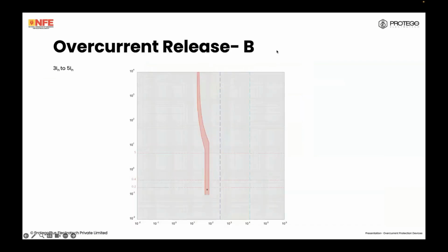Now, if we look at our overcurrent release, we know a B curve MCB trips between 3 to 5 times IN. For C, it is 5 to 10. For D, it is 10 to 20. Now we need to say what current will the OCPD definitely trip under. So we assume the higher value. For B, it is 5. For C, it is 10. For D, it is 20. Now we go back here. If you remember from earlier, for all these values, for B, there is only a single current causing disconnection because it is instantaneous, 0.1 second. For C, same story here. But for D, there's a different value for 5 seconds.